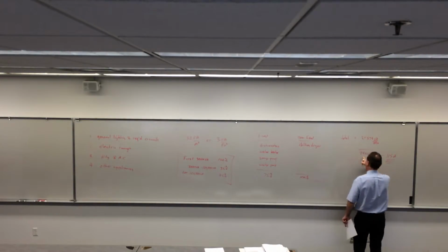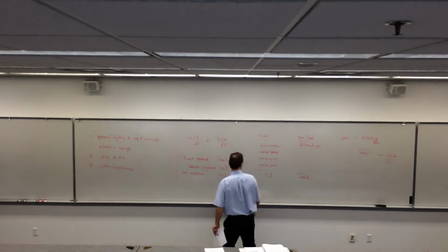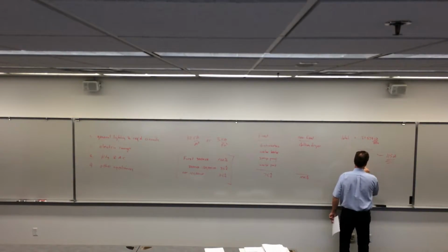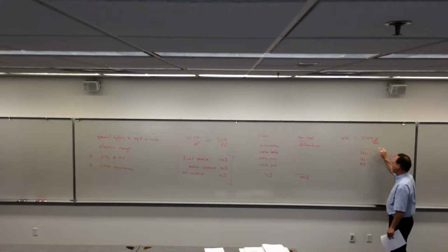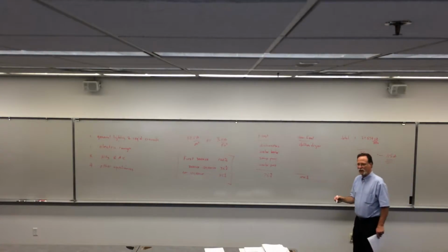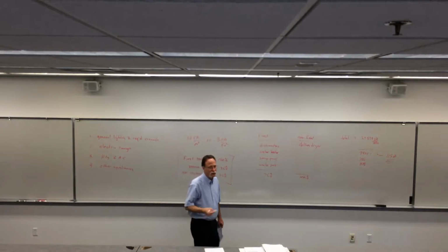And so you work through the examples, you end up with this total number, divide through by your service, which, typically in our residences and our rural environments, could be 240, it could be 220, it could be 208. One of those three numbers. So you have to know what's coming into your building. If it's 240, you get 115 amps. So if you have 115 amps, what kind of box do you buy? Next size above that, which is 150. You don't know that, but get a little experience and you would.